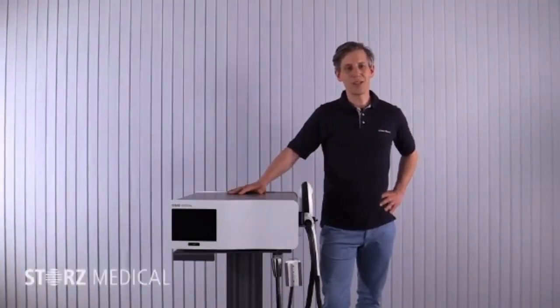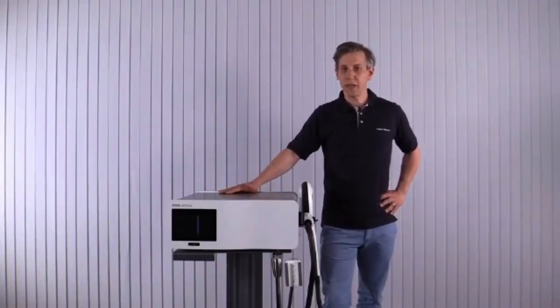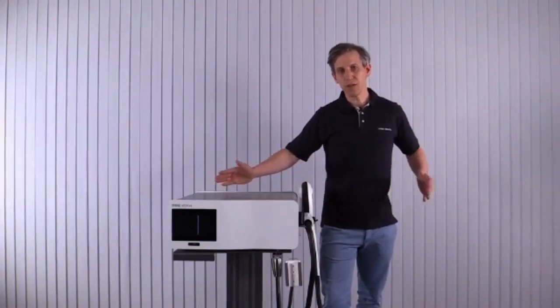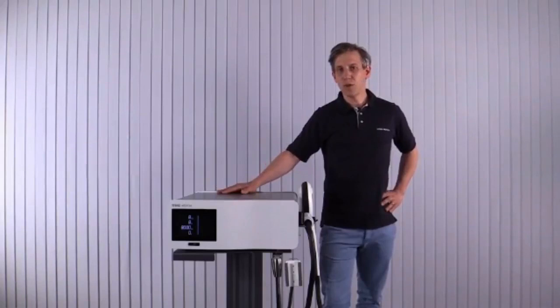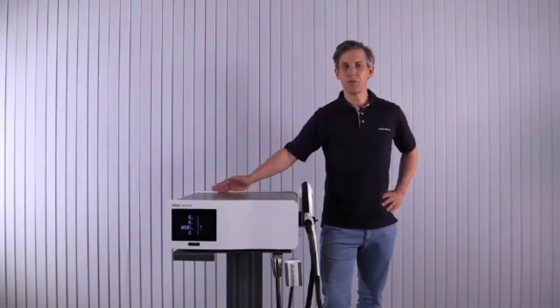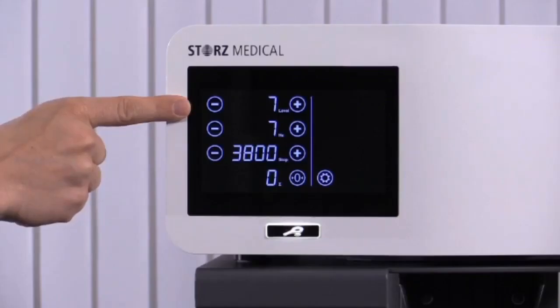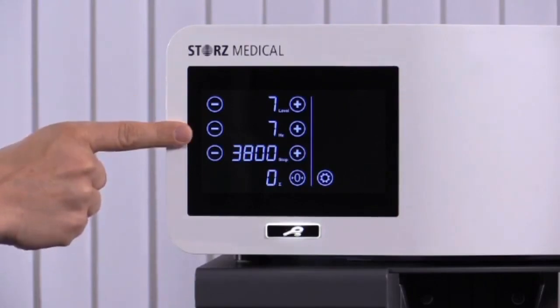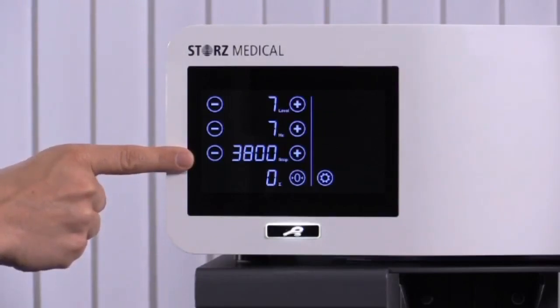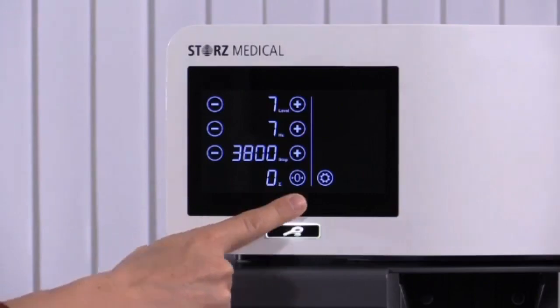To get started, switch on the device at the back. The startup takes approximately 20 seconds. Please note the user is prompted to conduct a high voltage test once a day. This test checks for any interference and the energy levels. Now let me explain the core functions of the user interface for defining treatment parameters. You can set the energy level in 6 steps, from level 3 to level 8. In the second row, you adjust the frequency of the pulses from 1 Hz to 10 Hz, where 10 Hz equals 10 pulses per second. In the third row, you define the maximum pulses per treatment, and this limit can be adjusted while treating the patient. On the bottom left, you find the pulse counter, and in the middle...